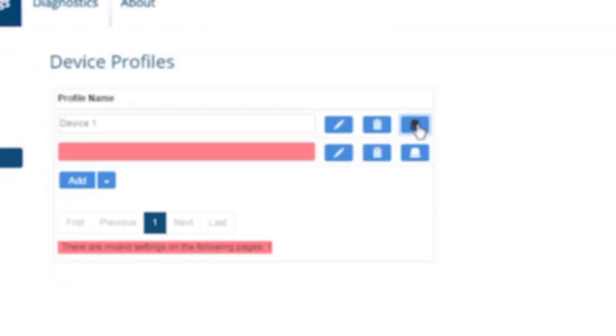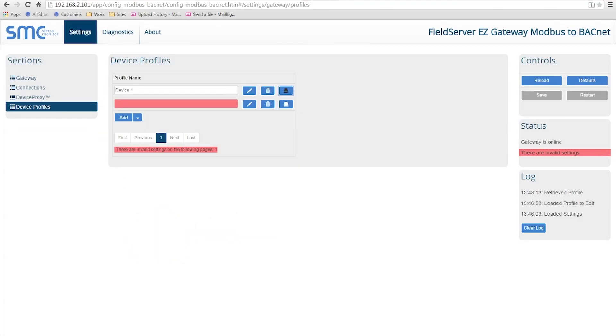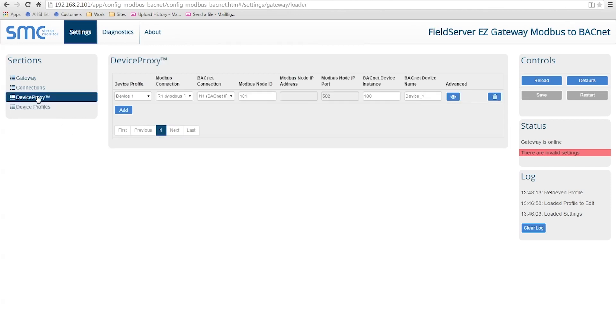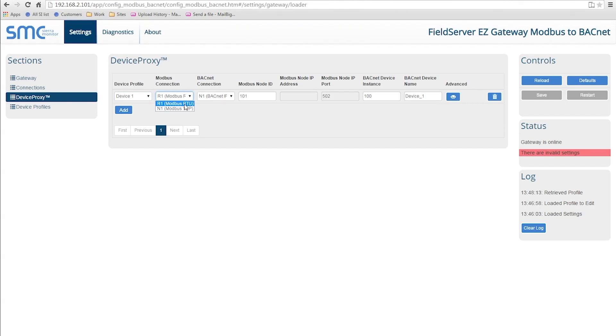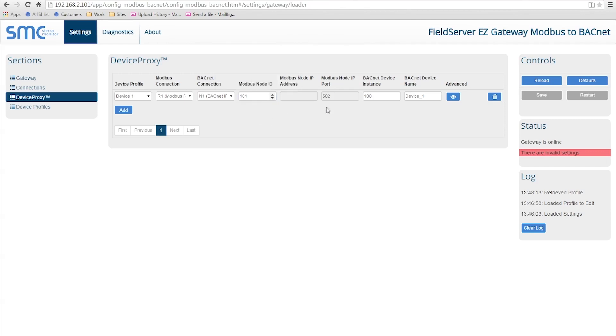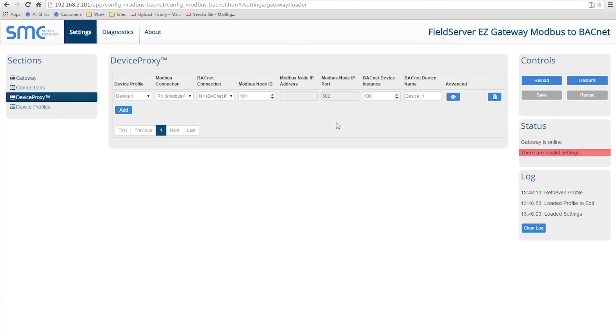Once you create your profile, you need to use Device Proxy to enable it on your EZ Gateway. To load your profile, choose the Device Proxy section. When you load the profile, you need to specify the type of Modbus connection, whether it is Modbus RTU or Modbus TCP/IP along with a Modbus Node ID. You also need to specify the BACnet device name and device instance.